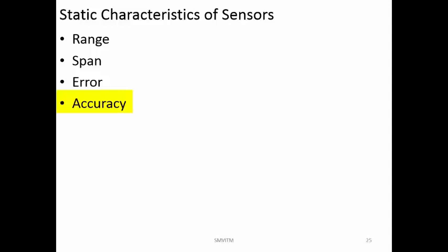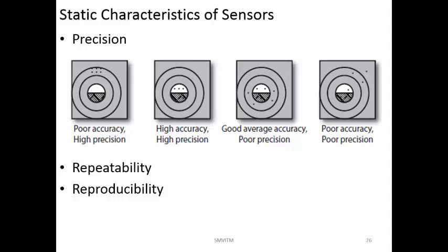Now what is precision? Precision is usually a combination of two other characteristics, which are accuracy and repeatability. So we'll see what repeatability is. Say you are trying to measure a particular dimension, or a particular voltage or current, and you are taking the reading repeatedly. How close the values are coming will give a measure of the repeatability of that particular instrument. Then you have the accuracy. So we'll see this from the figure.